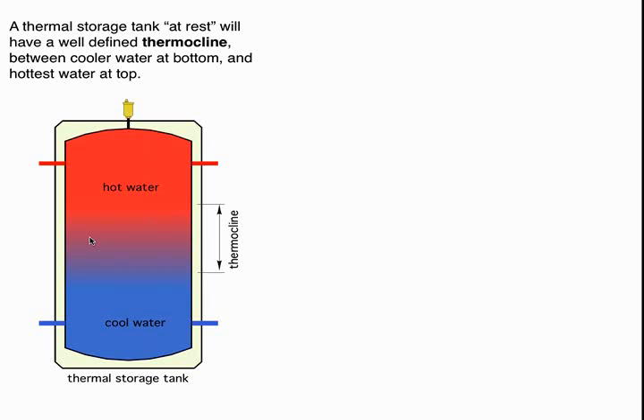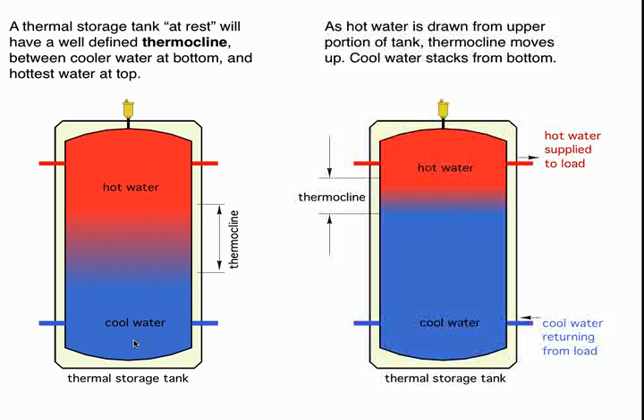If you have a building with a low temperature distribution system, the lower the water temperature that can still heat the building, the better, because it allows us to drain the storage tank to lower temperatures, and that gives us a wider temperature swing on the tank. So that's our on condition. And then our off condition is going to be when the bottom of the tank, or a sensor close to the bottom of the tank, gets up to a fairly high temperature.